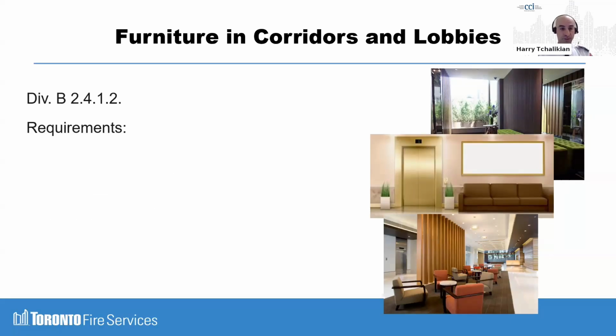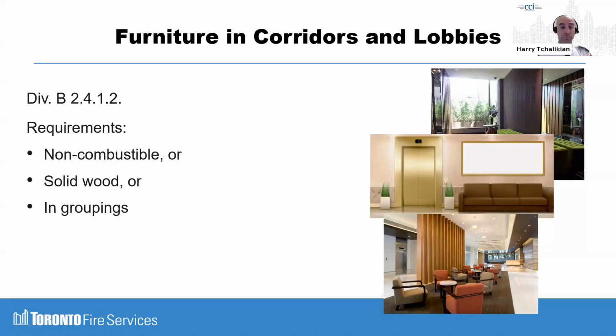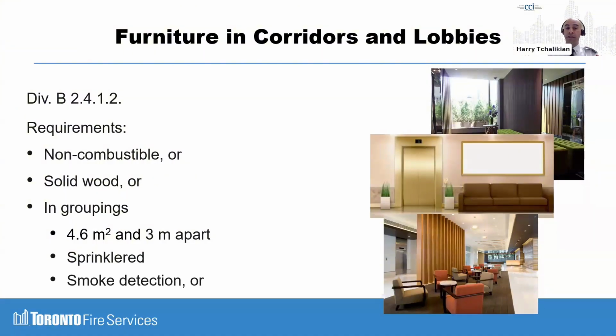So the requirements: the furniture is non-combustible or solid wood. So far not too comfortable or appealing. Or in groupings, maximum 4.6 meters squared and 3 meters apart. The space is sprinklered and there's smoke detection. So these requirements in the new fire code came from the City of Toronto's Engineering Technical Bulletin, which was a response to that Nielsen Road fire. After that fire, because the fire code was inadequate for dealing with this, we created our own internal engineering technical bulletin to address it, and that was pretty much adopted with these provisions.